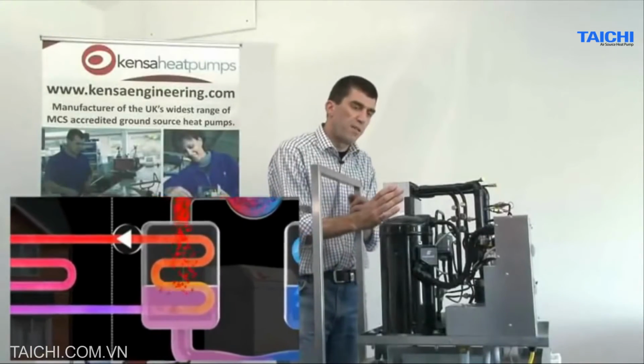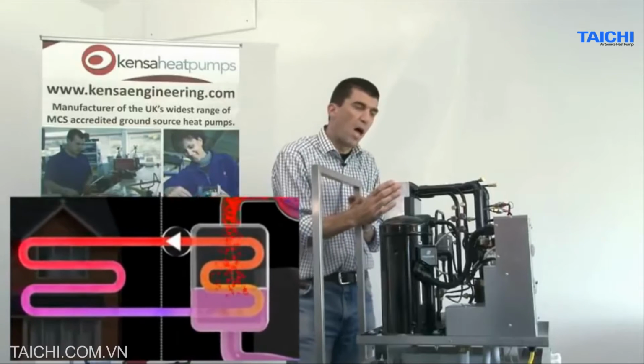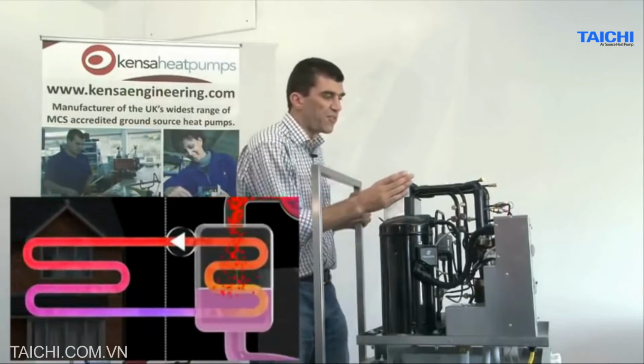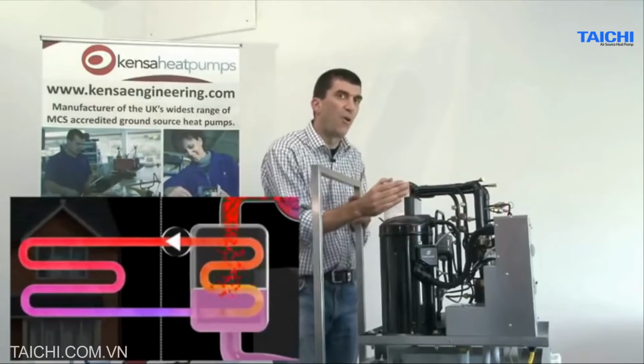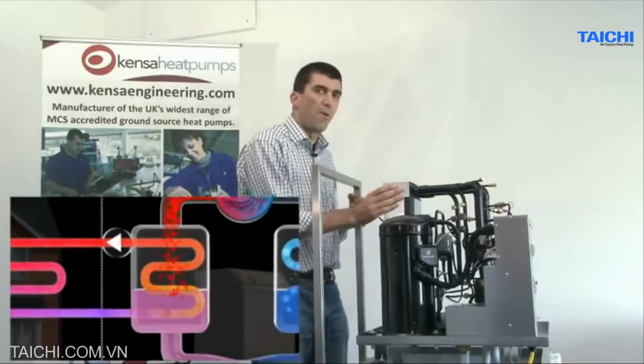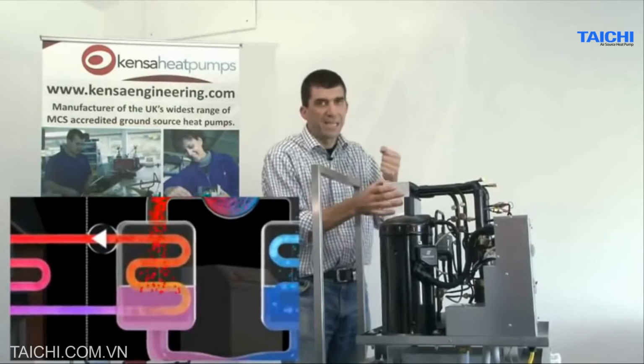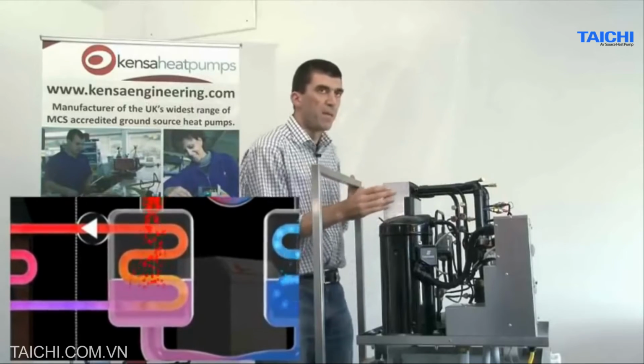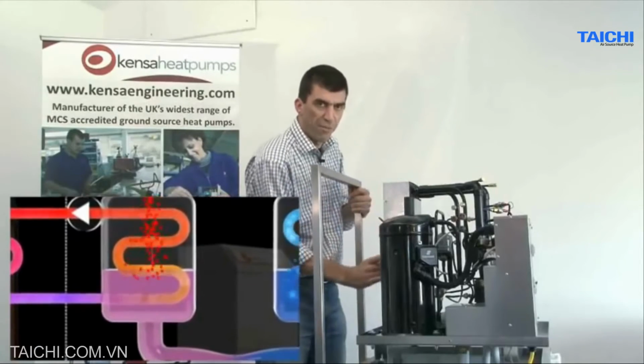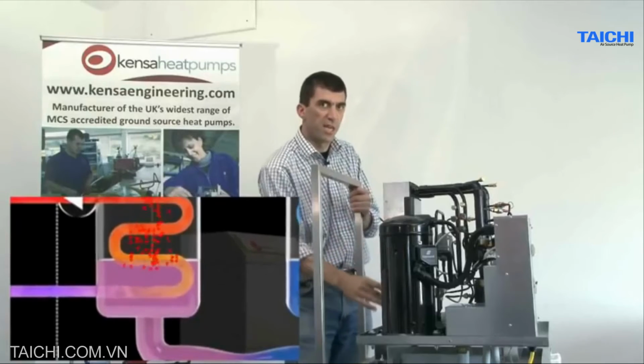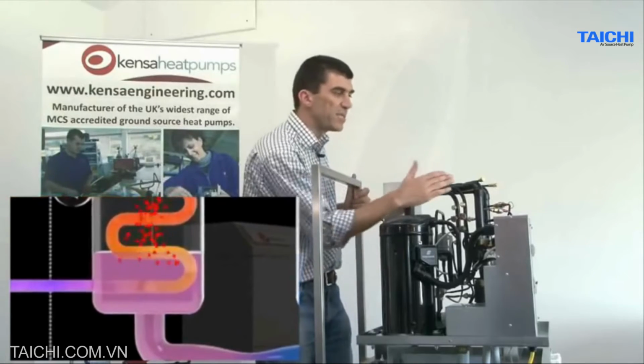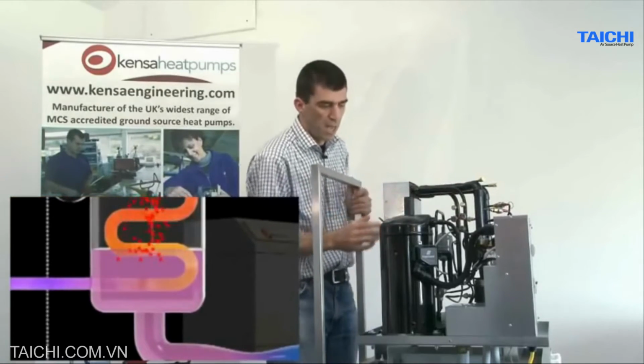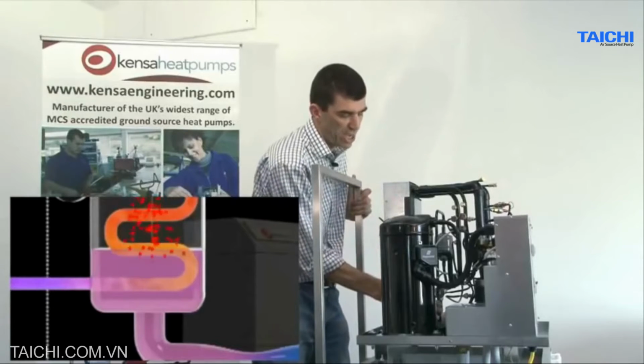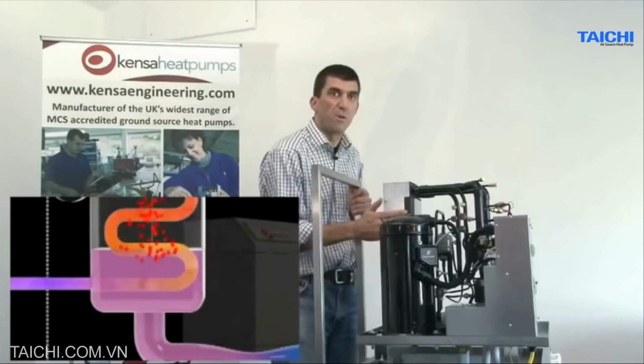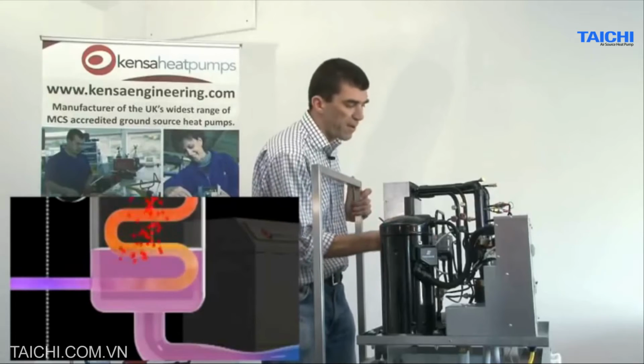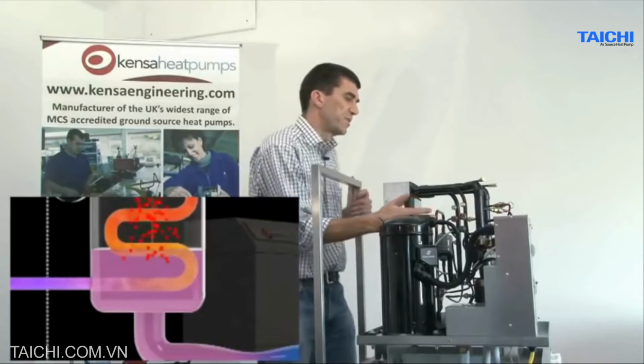Here, on one side of the plate, we have our underfloor heating water, and on the other side of the plate, we have our hot gas held under pressure. So it's a bit like we're in the gas bottle filling plant. The gas is being pumped in at the top here, but as the gas travels down through the passageways in the heat exchanger, it gives off its heat into the underfloor heating water, and by the time we get to the bottom of the heat exchanger, the gas has turned into a pure liquid. It's a liquid condensed refrigerant.